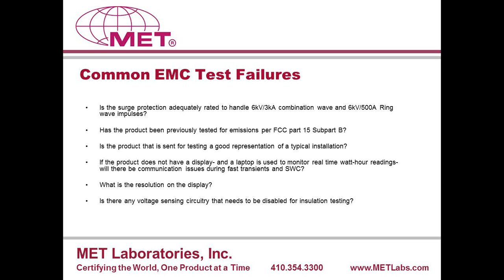Is there any voltage sensing circuitry that needs to be disabled for insulation testing? Sometimes this is one of the first series tests, test number 15, the insulation test, wherein we are checking the dielectric. When we perform this test, sometimes we are not aware beforehand of what the schematics is or how the product is designed. We will go ahead and perform the test according to the standard.